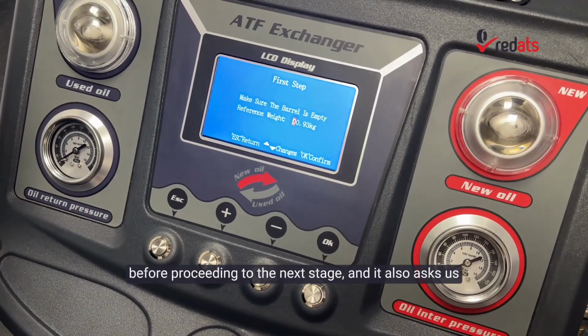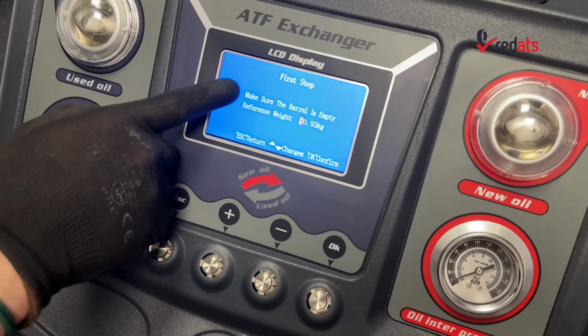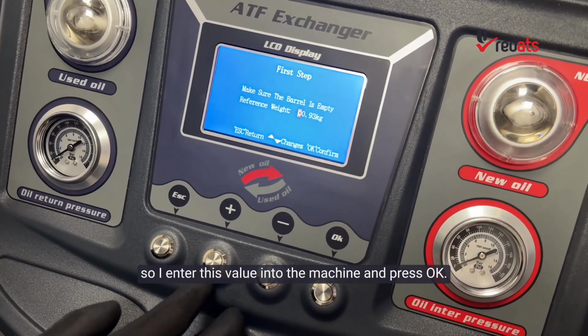The machine informs us that the tank must be empty before proceeding to the next stage, and it also asks us to set the weight of the calibration load. As I mentioned earlier, I have exactly 1 kilogram here, so I enter this value into the machine and press OK.